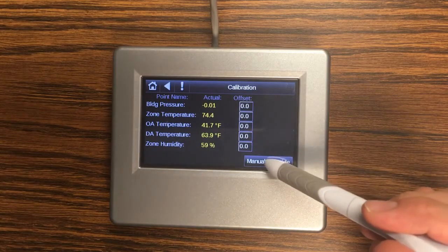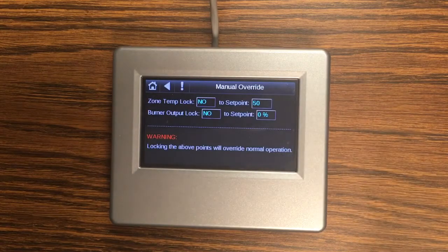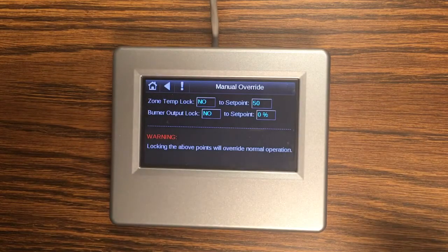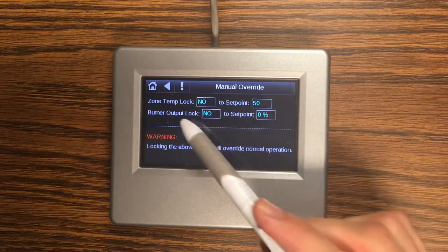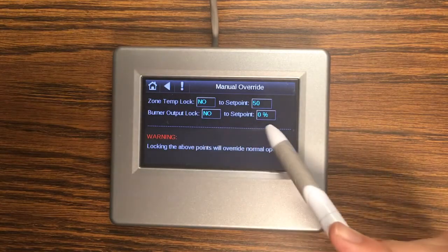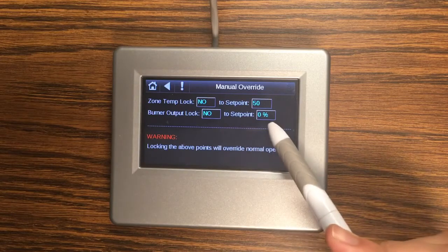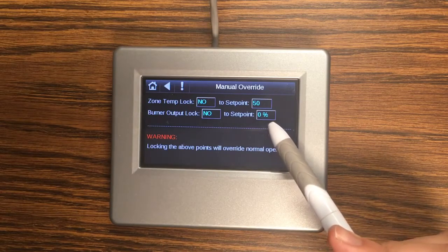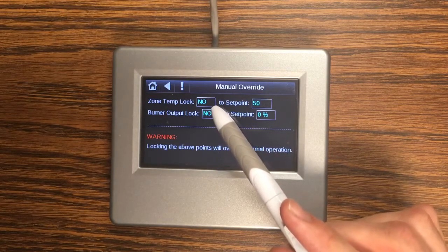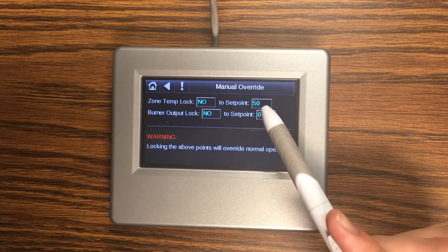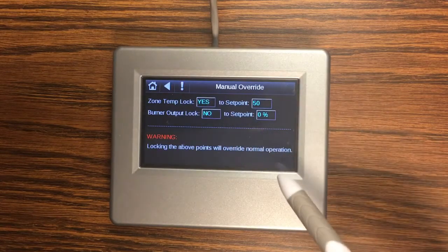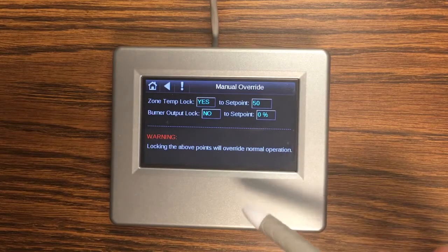We also have this manual override screen which is where we can force a couple values that are useful for troubleshooting. So we can change our zone temperature and we can change our burner modulation. So if we wanted to force high fire we could use this or if we wanted to check operation based on zone temp we could change it here as well. So to use this you set the lock to yes and then put in the value you want.